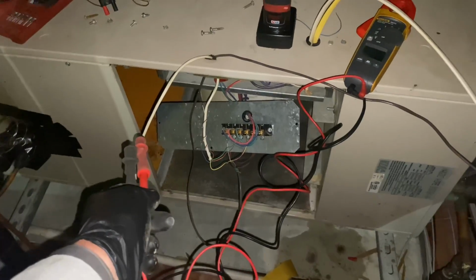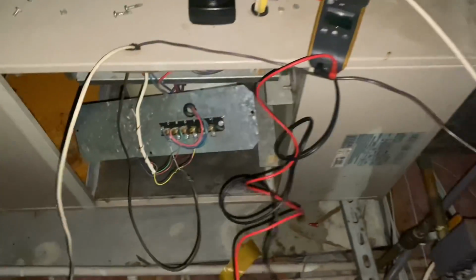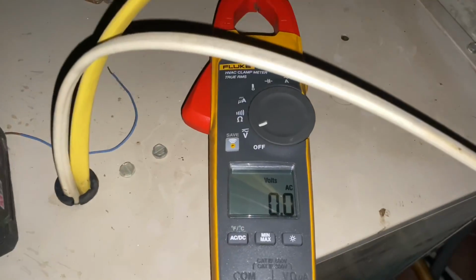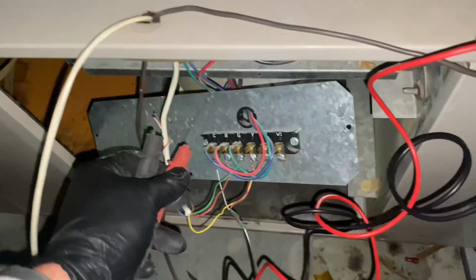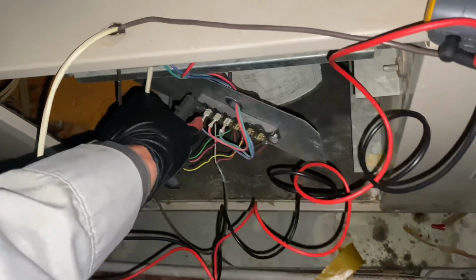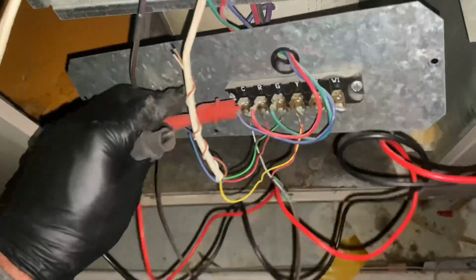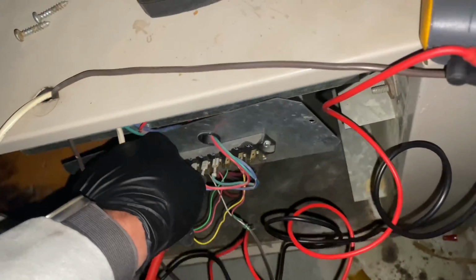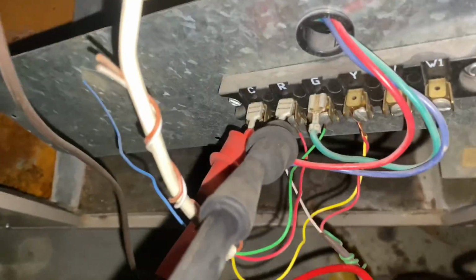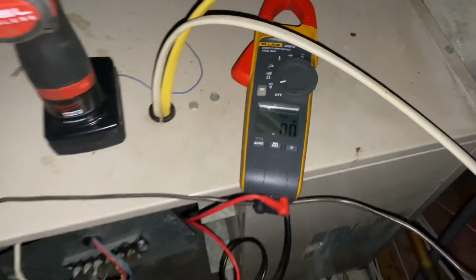All right, so I removed the blower compartment door because that's where my line voltage is going in. And one of the first things we're going to do, I got my Fluke 902 FC multimeter. We're going to take a voltage reading, if I can get in there, on R and C, and we're going to see if we have 24 volts. And we do not have 24 volts.